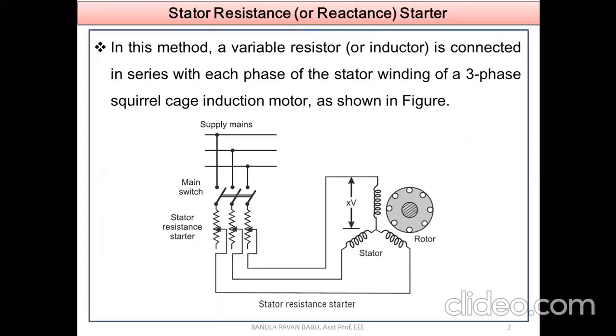If you are not applying equal resistance at each phase, it may create an unbalanced condition. If it comes to the unbalance, additional losses will be there, of course. Along with that, negative sequence components will exist. That is not discussed right now, but that is the main problem. If the three-phase system is unbalanced, there exist sequence component currents.